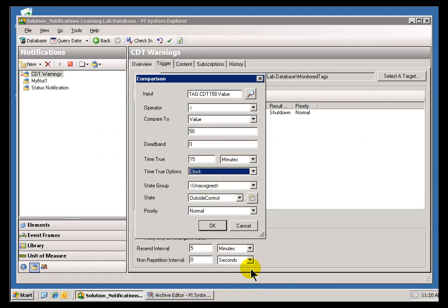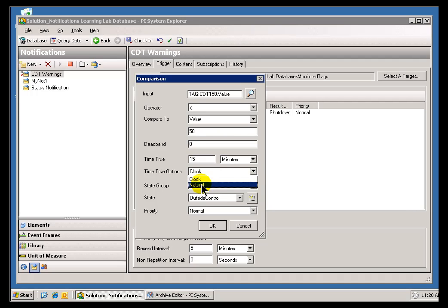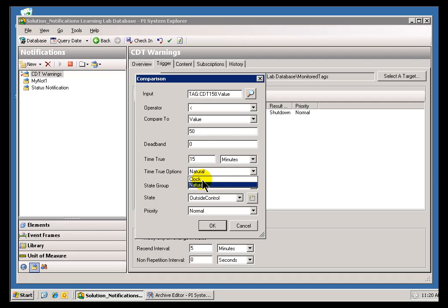That's a real obscurity, but that's the nature of this option. Clock simply means that after 15 minutes we'll send it. Natural means that we'll wait 15 minutes, but then after that 15 minutes is up, we will wait until the next value comes in to this Input Tag, and then, and only then, will we send the Notification.